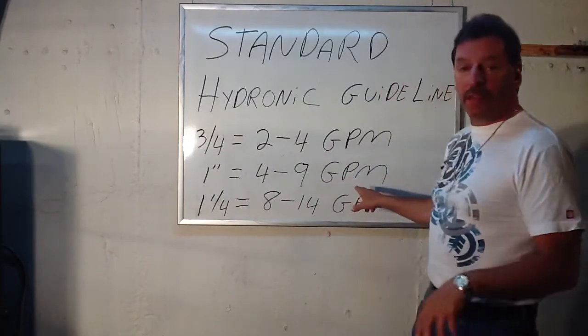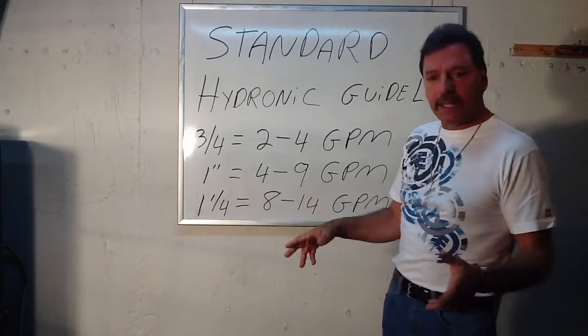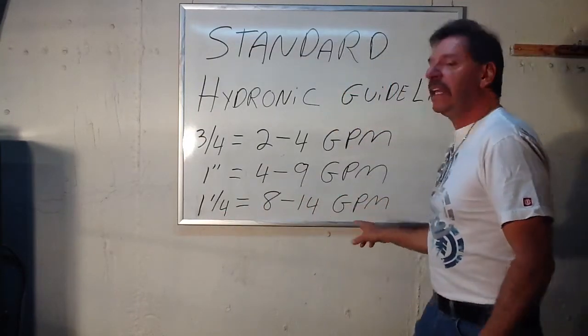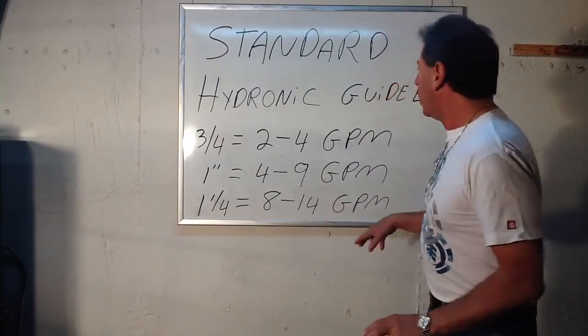If you needed more than that for some astronomical reason, maybe you're doing the Empire State Building, inch-and-a-quarter will give you eight to fourteen gallons a minute. An inch-and-a-half will give you fourteen to twenty-two gallons a minute.